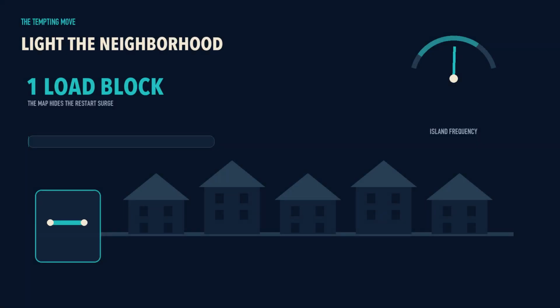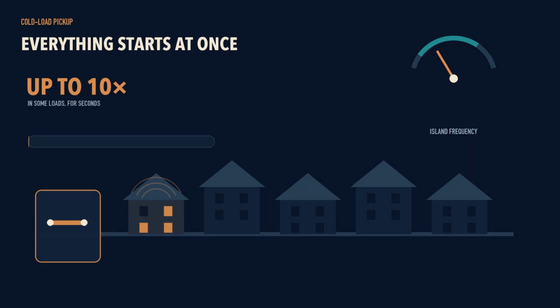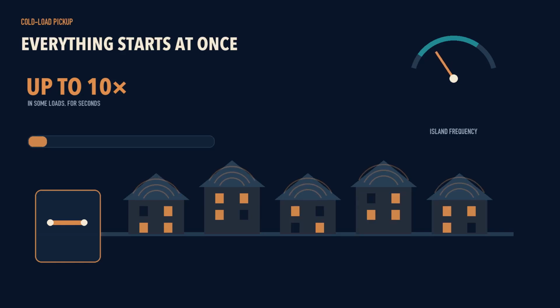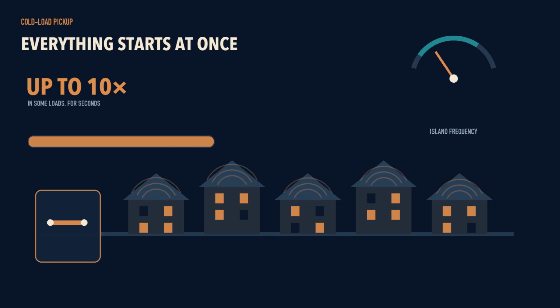The obvious next win is emotional. Light an entire neighborhood. Thousands of dark windows would switch on together. The feeder looks small enough on the plan. You approve the pickup. During the outage, thermostats kept asking for cooling, compressors stopped mid-cycle, pumps lost pressure, and motors cooled down. When power returns, many devices restart together. In some systems, the first surge can reach up to 10 times normal for a few seconds.